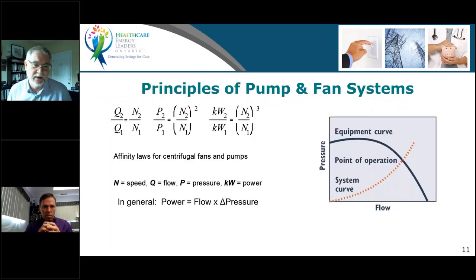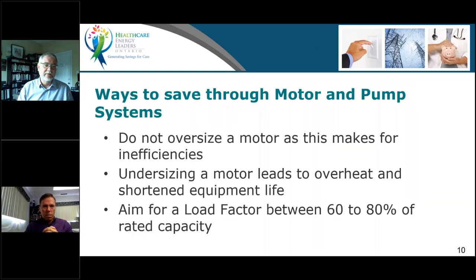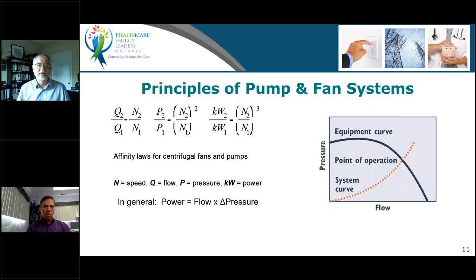So we're going to turn our attention to pumps, because I think there's a lot more opportunity with pumps. Honestly, I've gone out and changed motors to get efficiency improvements. We did a little experiment a number of years ago. We put more efficient motors in, but in 9 out of 10 of the replacements we did, we ended up taking them out and putting the old motor back, because it was the driven system that really dictated what was going on. So don't start with the motor. I've done it, and I've had to literally change motors out to fix the things we created by putting them in. So it's not a good idea. You've got to look to the driven system.